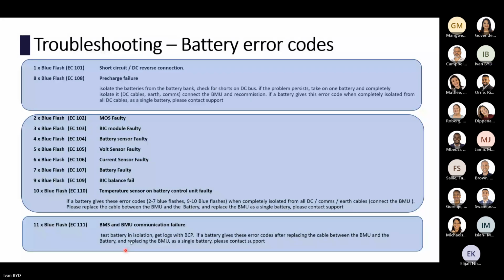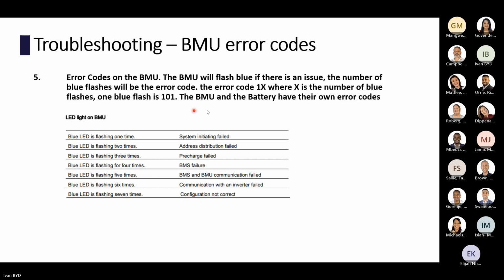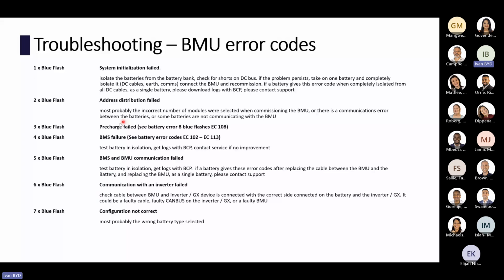And then there's this error code also the installer can do something with, which is the BMS and BMU communication failure. Here we've got the BMU error codes. The BMS error codes and the BMU error codes are different. So here we can see the BMU error codes. A lot of them reflect what the battery is seeing. For example, pre-charge failed is very similar to what the battery is showing with the pre-charge failure. Address distribution failure means that the BMU is commissioned for a number of batteries that it's not seeing. So for example, it might be more or less.